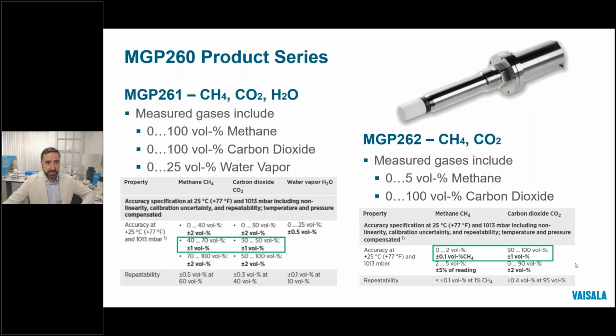The MGP 260 series currently consists of 2 probe models with others in development. The MGP 261 is our full-featured model with full range measurements of methane, carbon dioxide, and water vapor. It has a plus or minus 1% accuracy for the methane and CO2 at typical digester output levels, and a plus or minus 0.5% by volume water vapor accuracy, which is about 3 degrees Fahrenheit or 2 degrees Celsius of dew point accuracy.